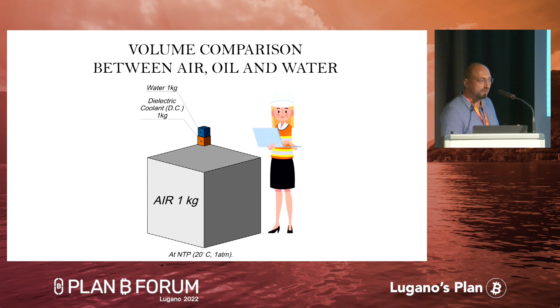This just means if we switch somehow to liquid coolants, we can use much less volume of that substance. The next page is about specific heat capacity. It shows how efficient air is compared to water or a dielectric coolant like oil in terms of cooling. We need to flow much more air in volume just to get rid of the same amount of heat than with water or liquid, and it's several times, many times, the difference.